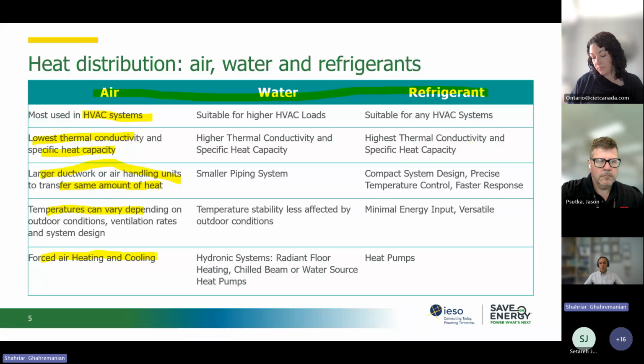And then, the forced air heating and cooling system is a very common one. Compared to air, we can use water, like a hydronic system. They can carry larger HVAC loads, and the reason is that water has a higher thermal conductivity and specific heat capacity, and because of this, we need only smaller piping to transfer the same amount of heat. Maybe I can touch on this one.